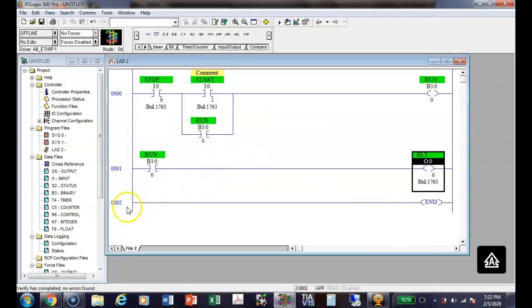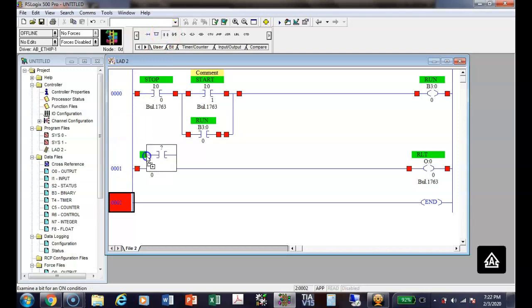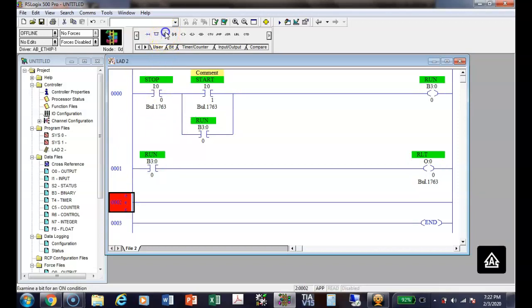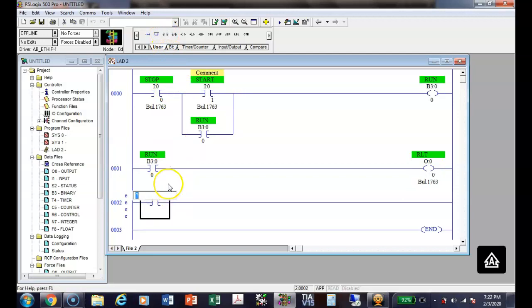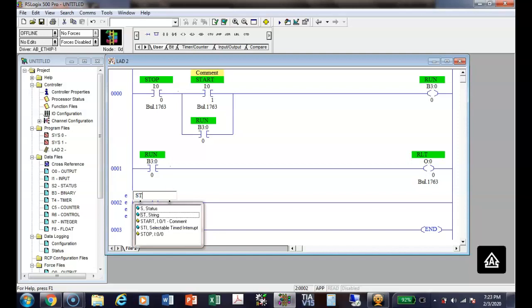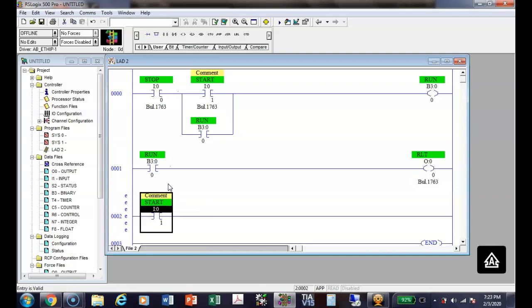We don't have to do this with PLC. So I can have a push button, just a single normally open push button out there. And all I have to do is just assign it to the same address. Oops. Got to insert another rung first, right? So I could come down here and my start button, I could come over here and just type in that. And how many times can we use, so I've only got one contact on my push button, but how many times can we use that address? As many times as you need, right? You understand that? So that's what's nice about a PLC.